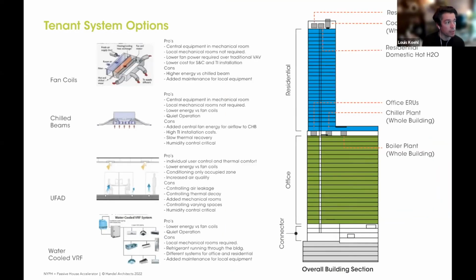We looked at a variety of options for heating and cooling for the tenants. Ultimately we're providing hot and cold water with the intent that tenants will use fan coils. Those fan coils will need to be ducted to the perimeter to wash the glazing, because due to the size of the glazing we're not meeting thermal comfort criteria with the glazing alone - tenants will be required to wash that glazing.